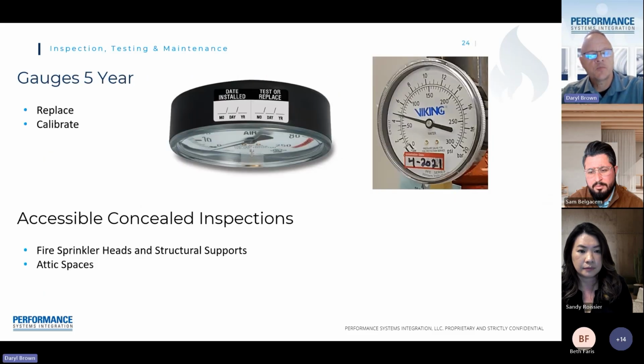Another last item we'll do on sprinkler systems is the calibration or replacement of gauges. These are gauges we utilize throughout the year for pressure testing to verify our water pressure is correct for providing pressure to our fire sprinkler heads as designed. Every 5th year, we need to check these for calibration. So it's either we remove and install a calibrated pressure gauge and verify we're within 3%, or replace them. A lot of times it's more practical to get them replaced every 5th year, depending on the number of gauges you have on your system.